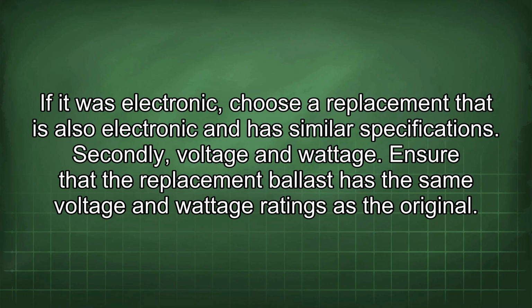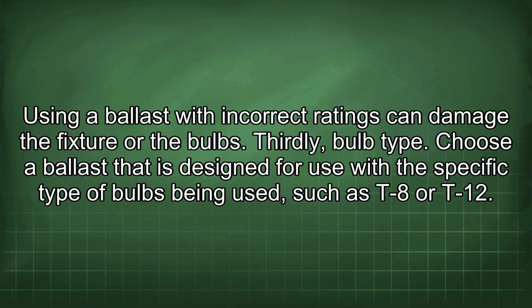If it was electronic, choose a replacement that is also electronic and has similar specifications. Secondly, voltage and wattage. Ensure that the replacement ballast has the same voltage and wattage ratings as the original. Using a ballast with incorrect ratings can damage the fixture or the bulbs.